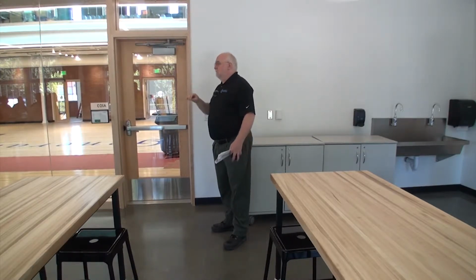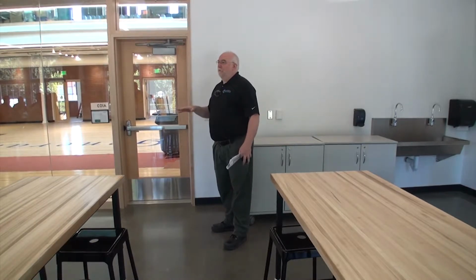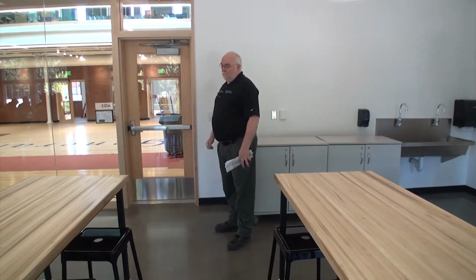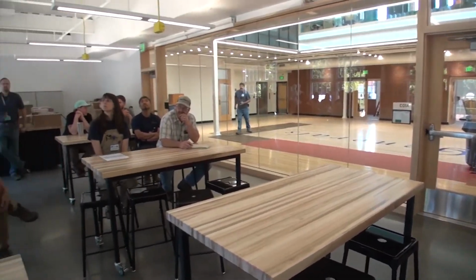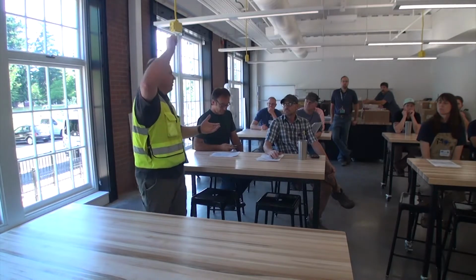And N-Light is not in every classroom, just FYI, but my understanding is they're all programmed the same way. So the other classrooms use sensor switch, which is the low voltage device. The sequence is the same as the N-Light ones, it's just that to program those you have to do push button programming - get into mode 1, 2, 3, menu 1 through 6. You guys are all like, you've been through this hell before.